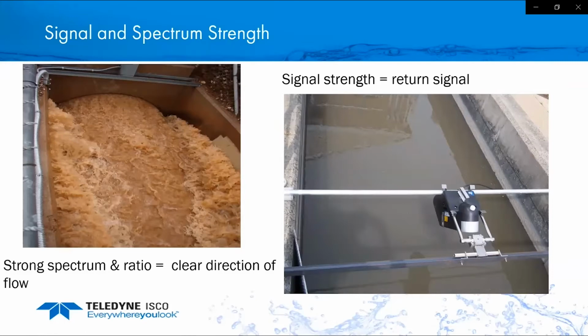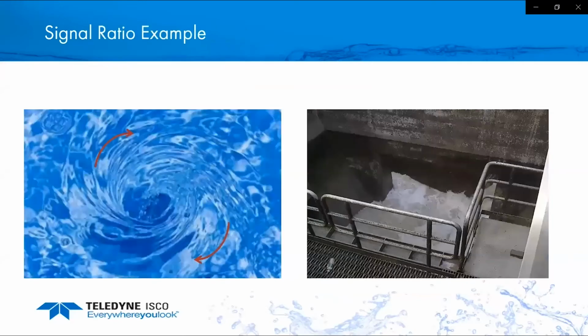And if there's a problem, like what we saw with that previous picture, as it starts to get covered, the signal spectrum strengths are going to start to drop. So that's where you want to look at the trend and determine when you need to go out and do maintenance. Now with the signal ratio, before I had a really strong signal because everything was going the same direction.